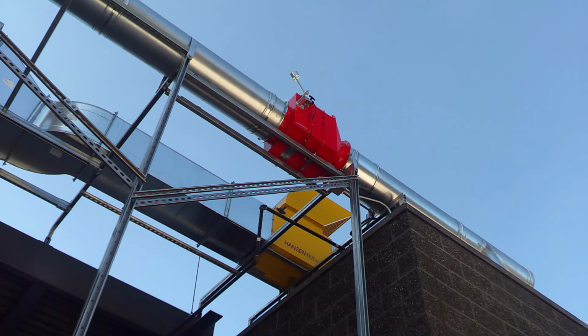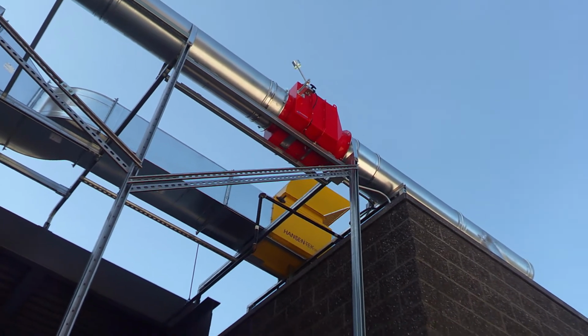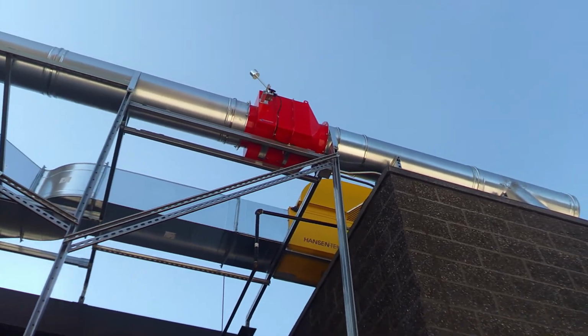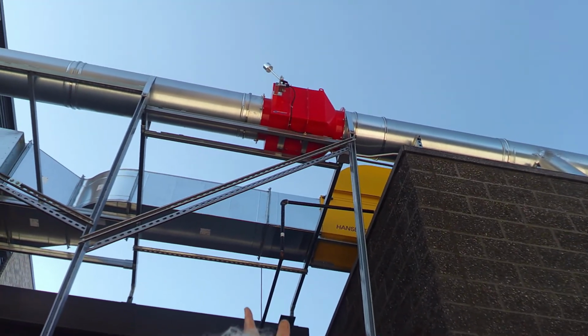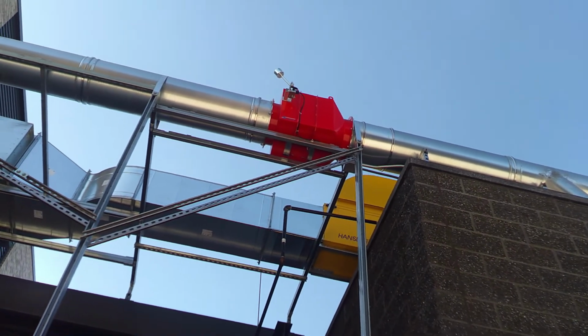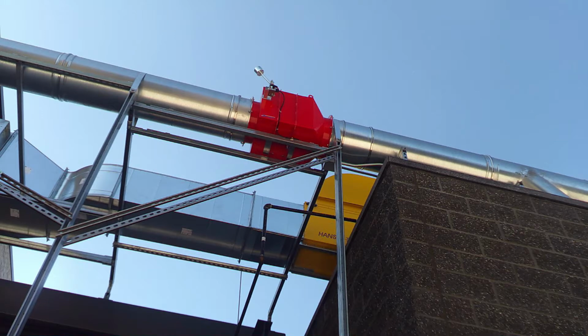In fact, those individual dampers that we looked at inside, those volume control things, have remarkably little effect. You can close them halfway and you get maybe a 10% reduction. So it would seem that would be much more restrictive than it is. But it's basically floating in there, so that if the air goes in the opposite direction, it very easily comes down and closes. And that handle, where you put your fingers, will swing down, and when the air pivots and closes the damper, that will lock in place. Then somebody has to go up and pull that handle out, and it releases it. It'll just go back up.